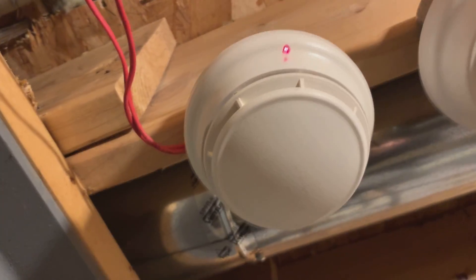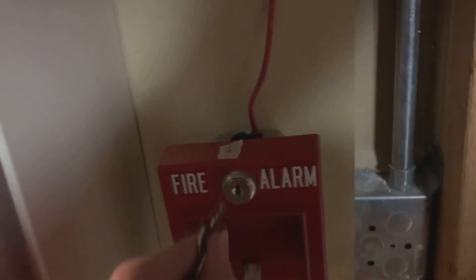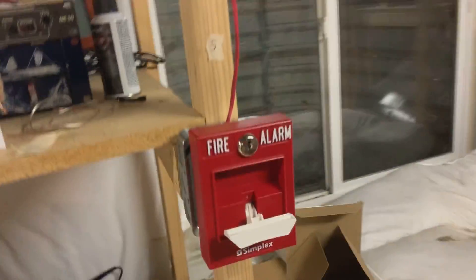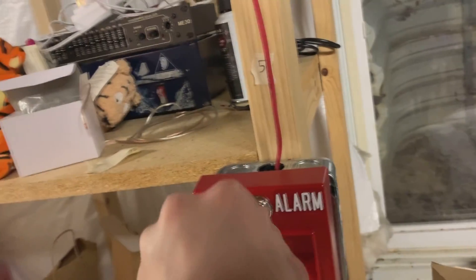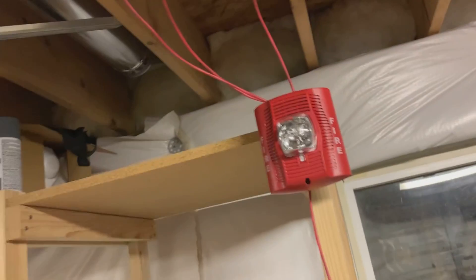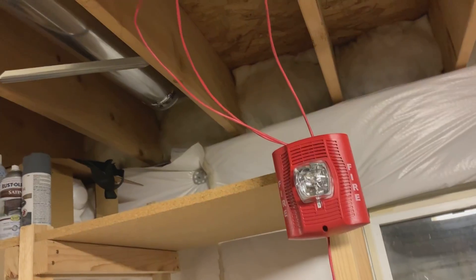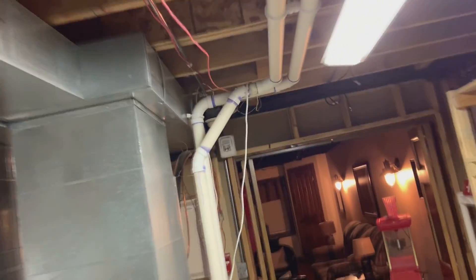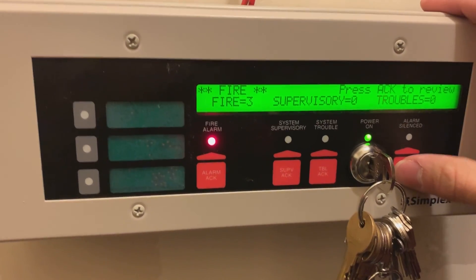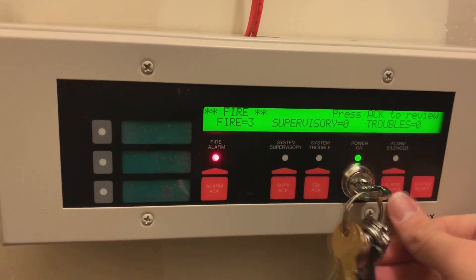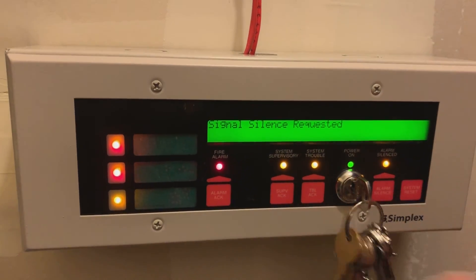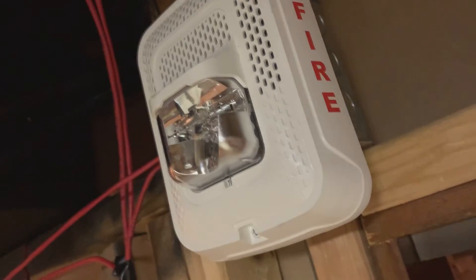Perfect timing. It's pretty darn loud. Let's go ahead and see if we can reset from the annunciator today. So I do have it set up to do audible silence. So that silenced the signals, they're still flashing though. Let's go back over here, didn't think this through. There you go still flashing.